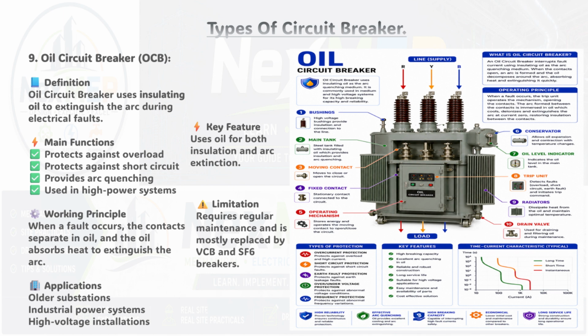This is one of the oldest types of circuit breakers still found in older power systems. Here, the contacts separate inside a tank filled with insulating oil. When the arc forms, the oil around it decomposes, generates hydrogen gas, which helps cool and extinguish the arc. So oil serves a dual purpose: insulation and arc extinction. OCBs are found in older substations, high-voltage installations, and industrial power systems. The voltage range is typically 11 kV and above.